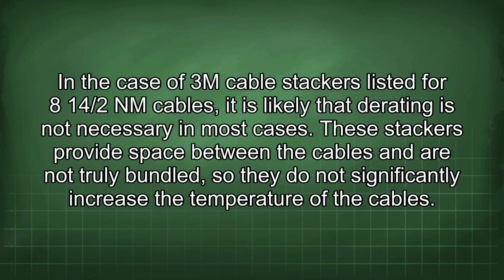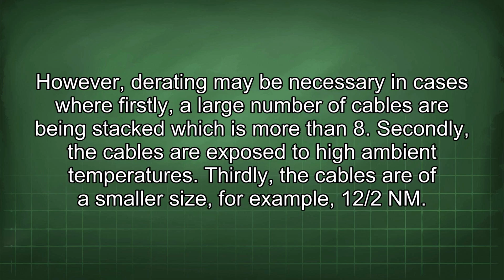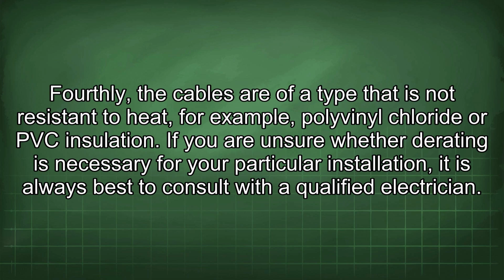In the case of 3M cable stackers listed for 8 14/2 NM cables, it is likely that derating is not necessary in most cases. These stackers provide space between the cables and are not truly bundled, so they do not significantly increase the temperature of the cables. However, derating may be necessary in cases where, firstly, a large number of cables are being stacked, which is more than 8. Secondly, the cables are exposed to high ambient temperatures. Thirdly, the cables are of a smaller size, for example, 12/2 NM. Fourthly, the cables are of a type that is not resistant to heat, for example, polyvinyl chloride or PVC insulation. If you are unsure whether derating is necessary for your particular installation, it is always best to consult with a qualified electrician.